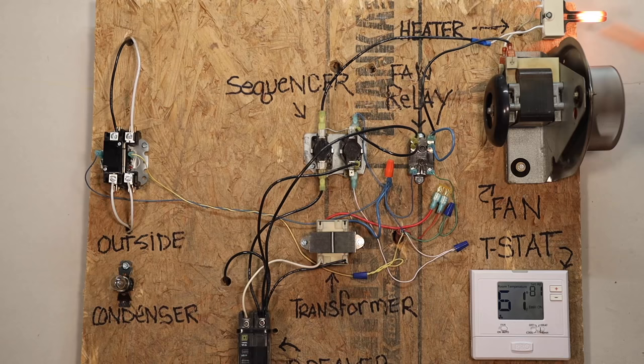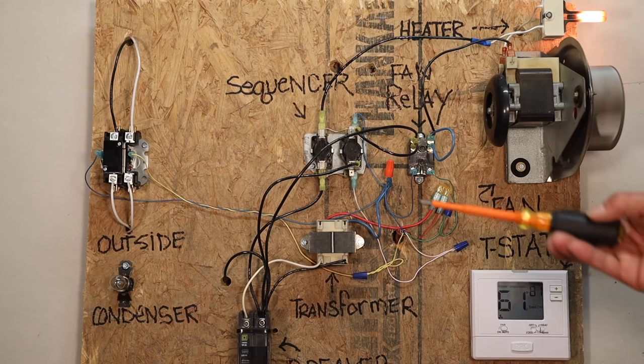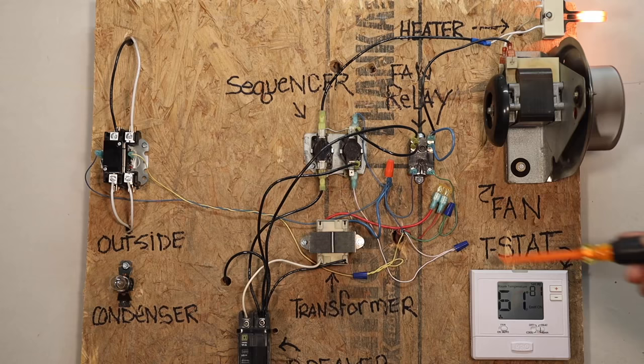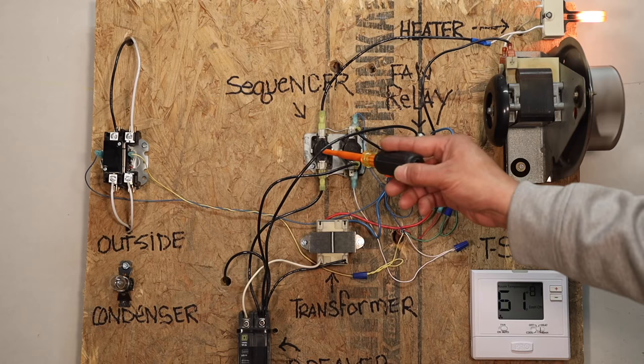So the reason for the time delay in the time sequence is this: when your heater turns off, or you turn your heater off, the first sequencer would de-energize first, turning off the heater. There will be no more 24 volts at the sequencer, so it would shut off, but it shuts off in a time sequence. So the first one that will shut off is going to be this one, which will shut off your heater.